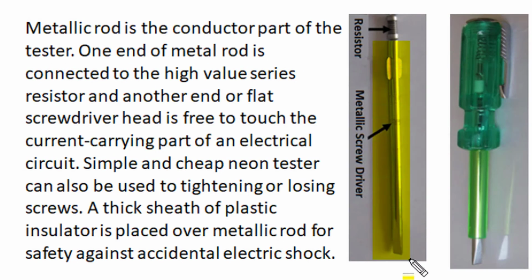This metallic rod is the free conductor part of the tester. The tip of it is given a screwdriver shape, and this tip acts as a test probe and is connected to the current carrying part of an electric circuit, whether they are phase or neutral connected. The other end of this metallic screwdriver rod is connected to a high value of series resistance in the internal circuit of the phase tester. In this economic and simple neon tester, we can use this screwdriver tip for loosening or tightening of screws available in electric wiring components or appliances.